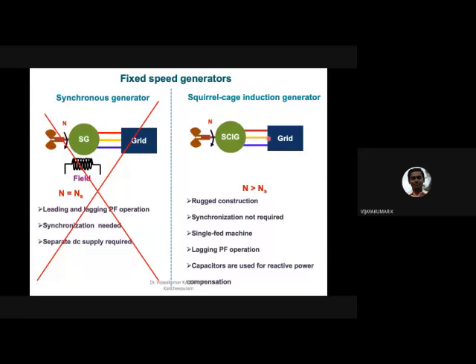One of the disadvantages of this system is lagging power factor operation. What does lagging power factor operation mean? It always takes reactive power from the grid, whether it operates as a motor or as a generator. If it is taking reactive power from the grid, then when you look at the power factor at the point of common coupling, it's lagging. So that's a disadvantage. To compensate this reactive power taken from the grid, people normally connect capacitor banks at the stator terminal of the squirrel cage induction generators, so that the capacitor banks provide reactive power compensation to the system and we can improve the power factor in this case, right?